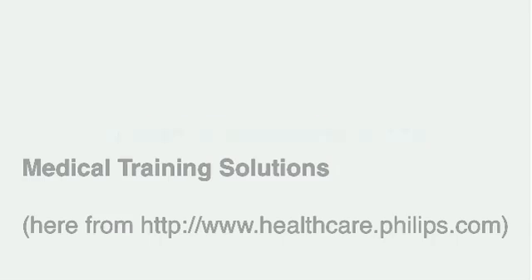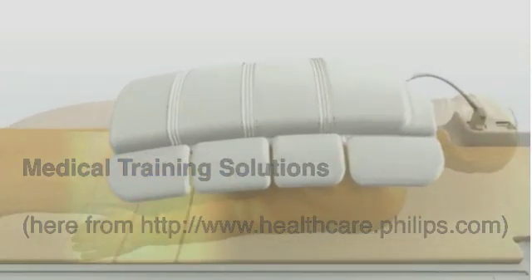The new digital coil design really elevates the clinical performance of the system because we digitize the signal right at the patient, and that maintains the purity of the signal. I can tell you that it makes a huge difference — it makes a difference in terms of 40% increased signal-to-noise.